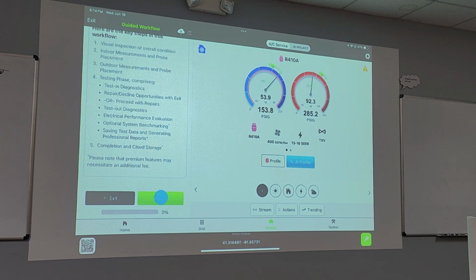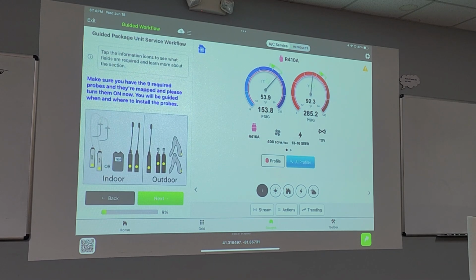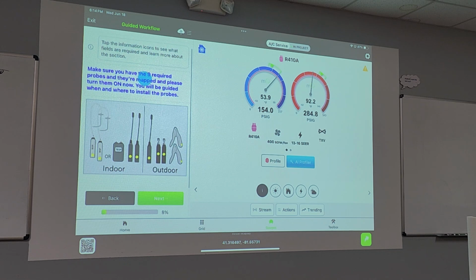If this were a new site, new equipment, this process would look exactly the same - the only exception is there's already data put in now. At this point, I have the probes hooked up and turned on the system, but if you're reading the directions closely, all it really says is that you need to make sure you have the 9 probes turned on. They don't actually have to be connected to the air conditioner, and it doesn't have to be running yet.